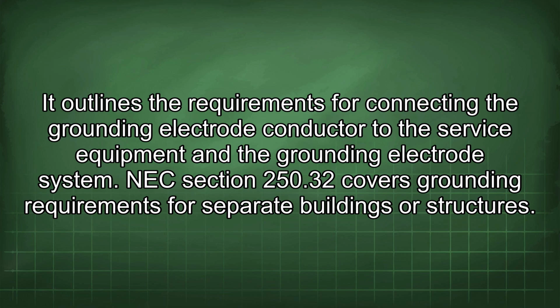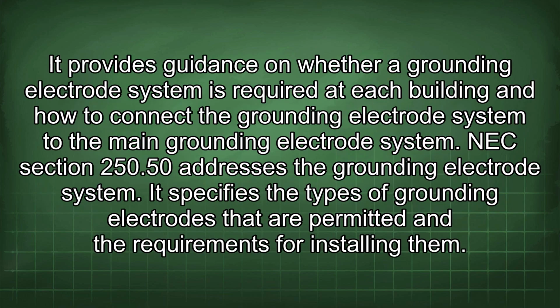NEC Section 250.32 covers grounding requirements for separate buildings or structures. It provides guidance on whether a grounding electrode system is required at each building and how to connect the grounding electrode system to the main grounding electrode system. NEC Section 250.50 addresses the grounding electrode system. It specifies the types of grounding electrodes that are permitted and the requirements for installing them.